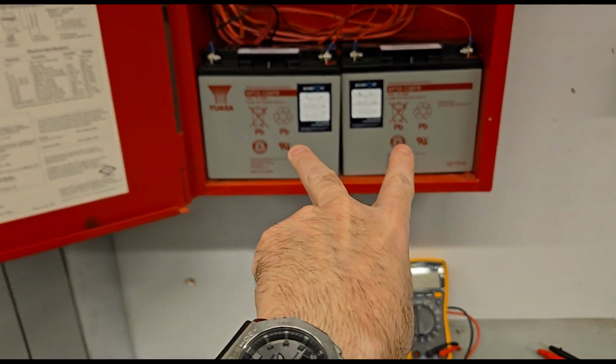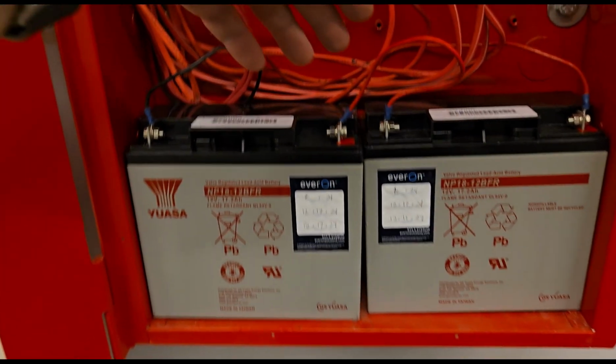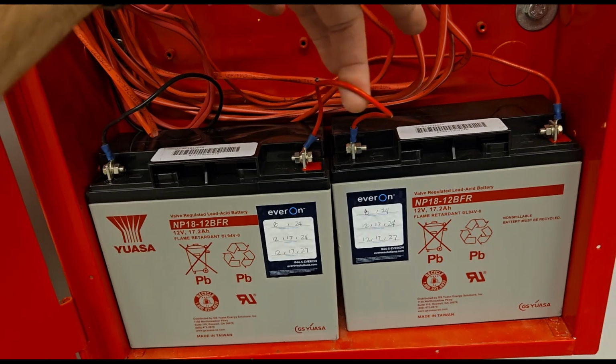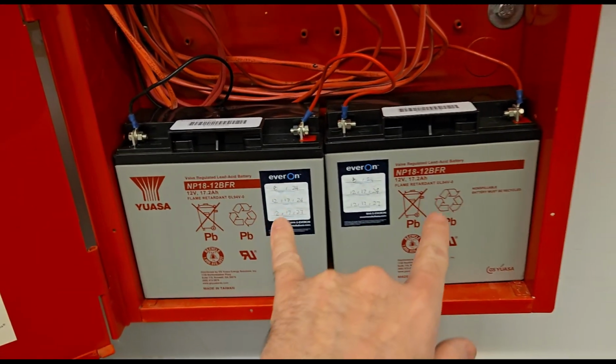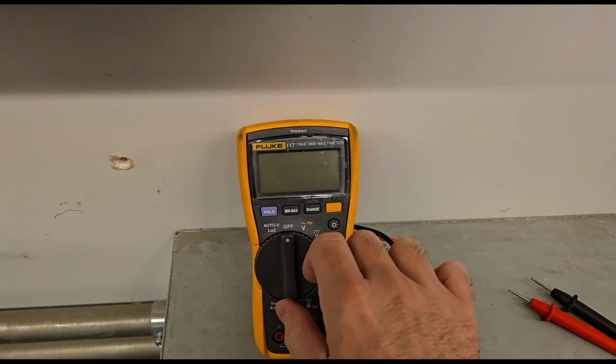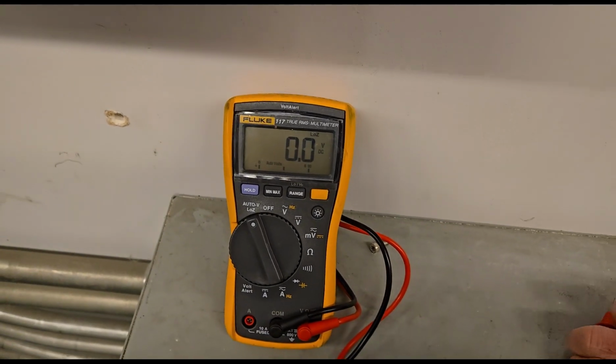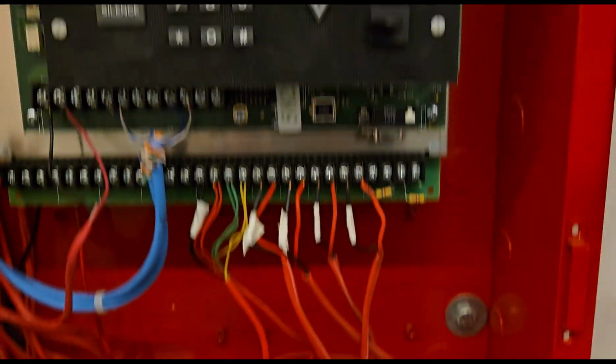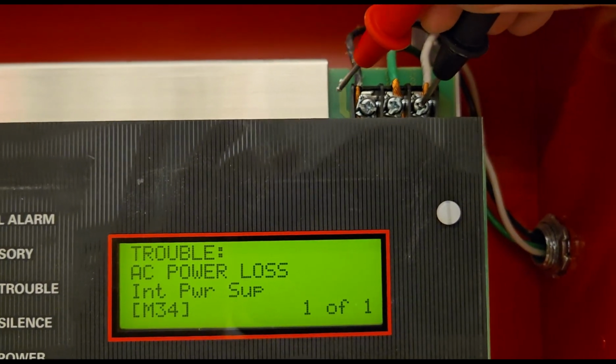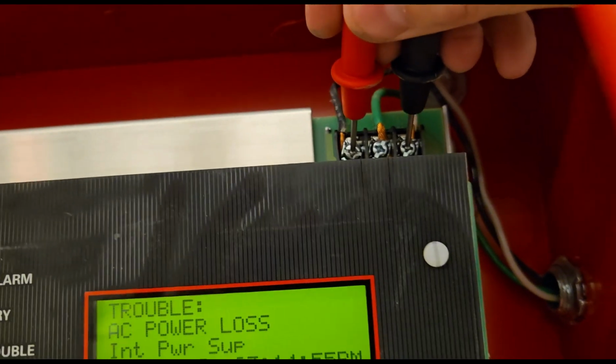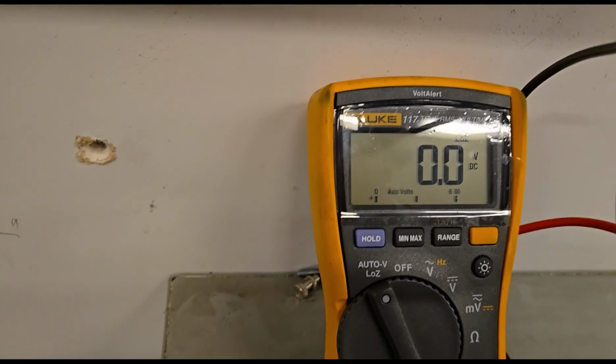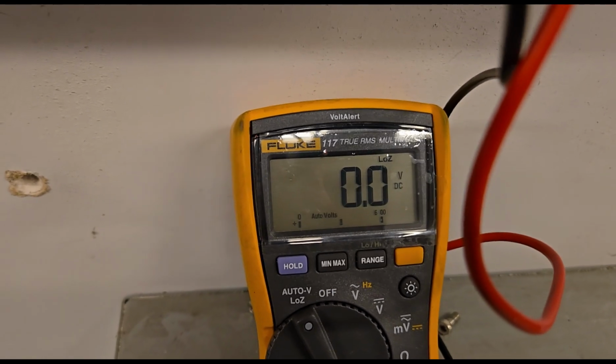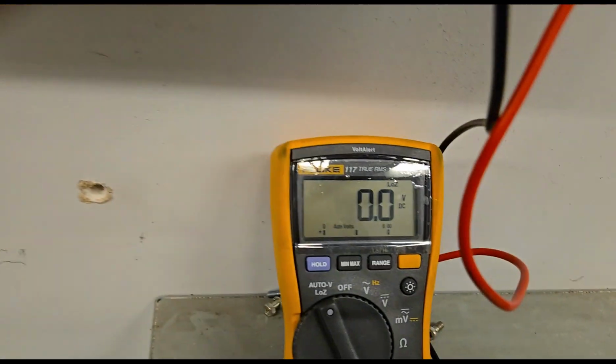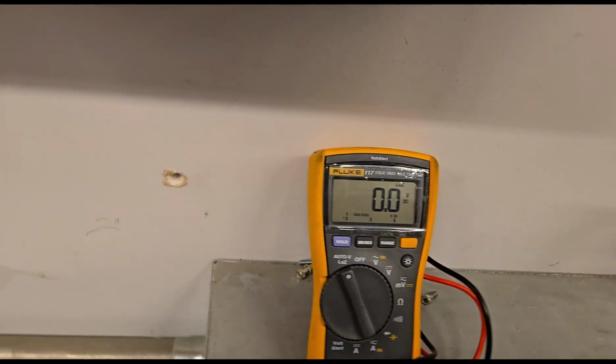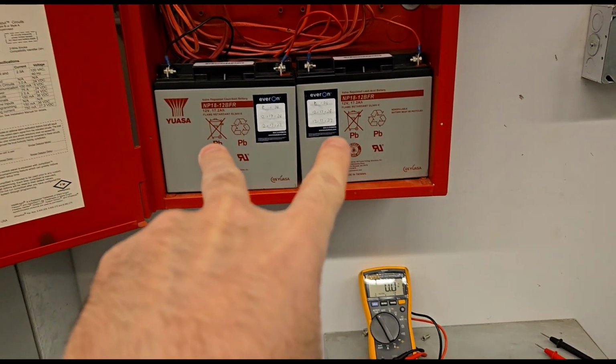So right now the system's running off the batteries, and this is two 12 volts put together. So it's a 24 volt system. I have my loop right here, so it's 24 volts. What we're going to do is flip our meter on, and we're just going to again take a measurement, our voltage reading I should say. Again, my chopstick skills, so I got both leads in, and you see on the meter it's 0, because again we have the AC power off. So I have my leads in, and we have no power. So we know that we did in fact kill the power, and we're running off our backup batteries now.